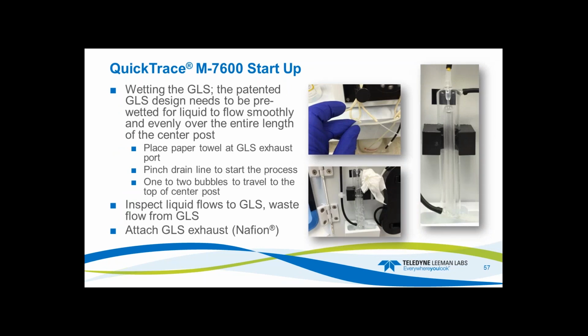The next step is to wet the gas liquid separator. So this is a patented design. It's a center post design, so thin film. So it's extremely efficient at stripping off the mercury and getting into the system. This is one of the reasons that our systems, or the QuickTrace 7600, can get down to less than 0.5 nanograms per liter as an instrument detection limit. For a CVAA system, that's almost unheard of.